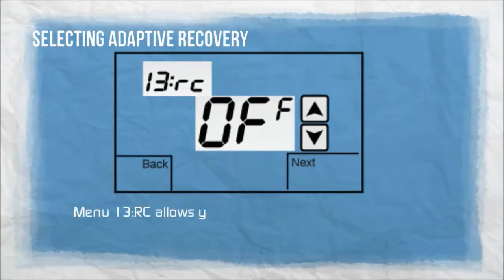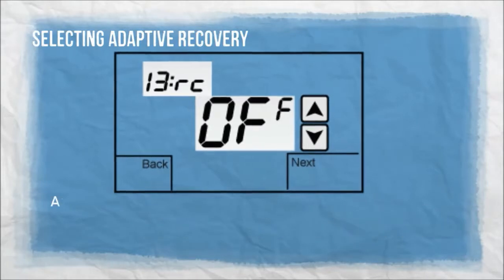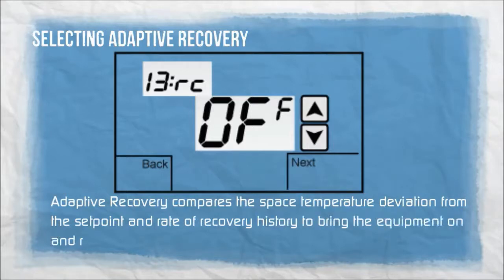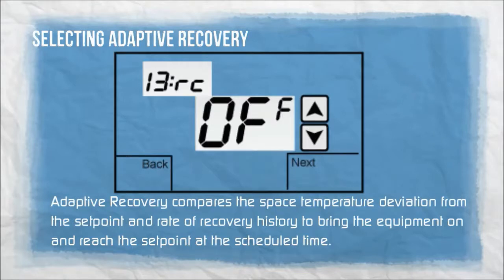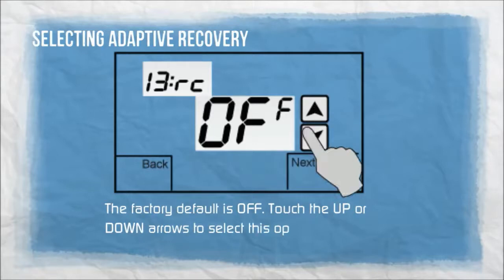Menu 13RC allows you to select the adaptive recovery option when the thermostat is configured as programmable. Adaptive recovery compares the space temperature deviation from the set point and rate of recovery history to bring the equipment on and reach the set point at the scheduled time. The factory default is off. Touch the up or down arrows to select this option.